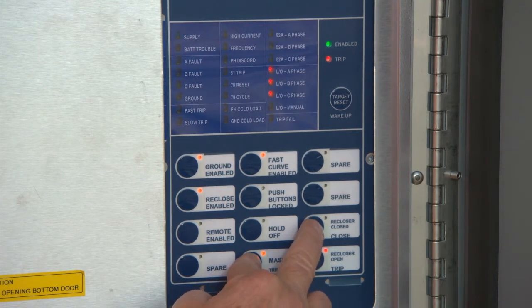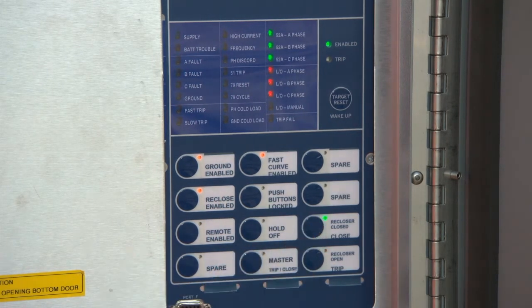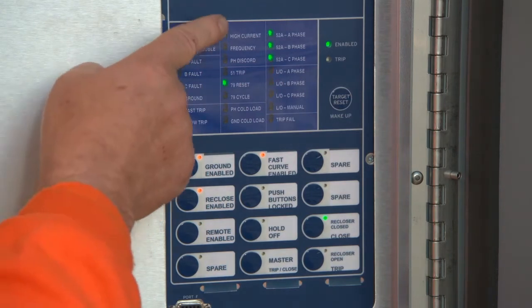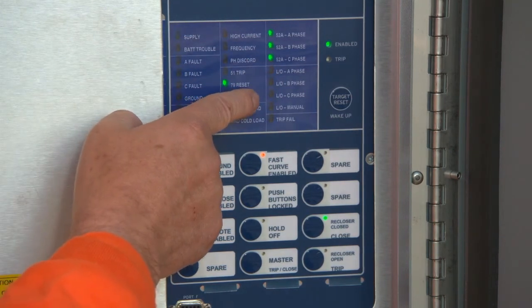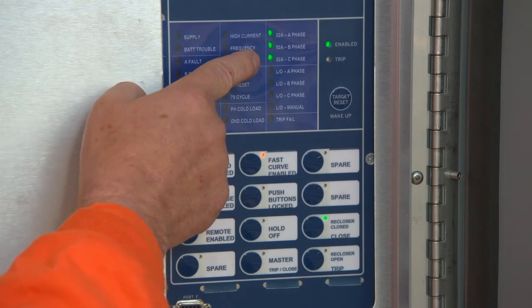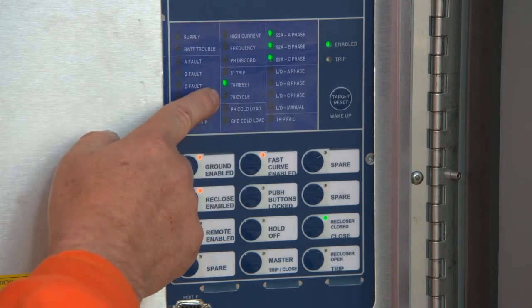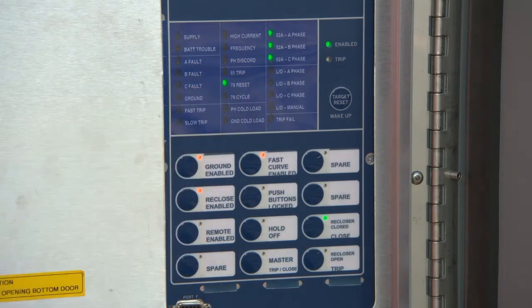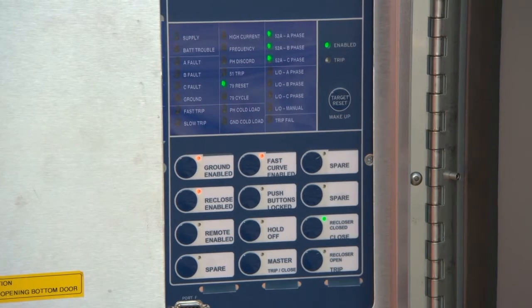Closing the control back in is also a 2-button operation. Push the master and recloser closed button together. The state will change from lockout to closed. The control will revert to a 79 reset state. It is now capable of full functionality.